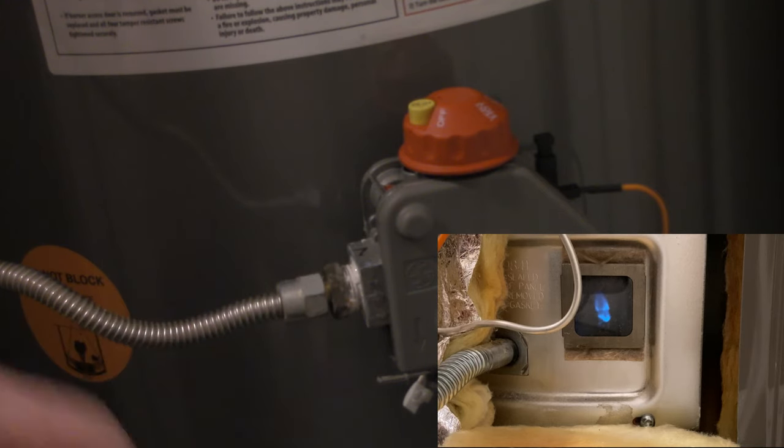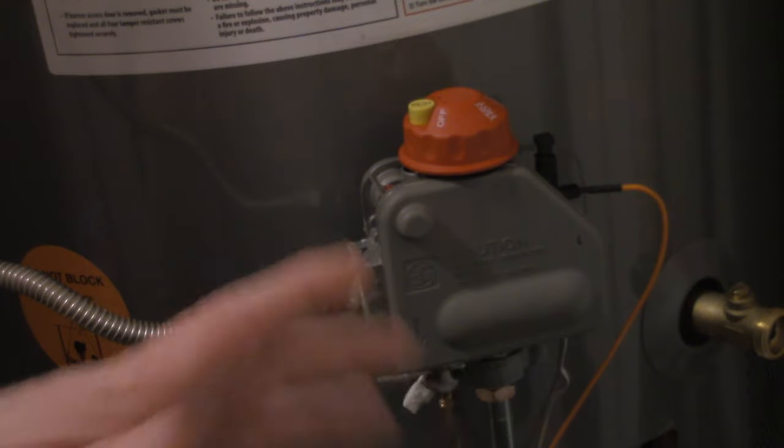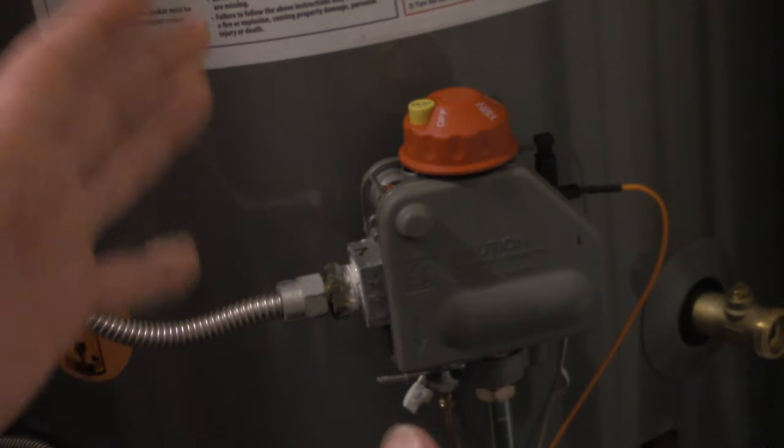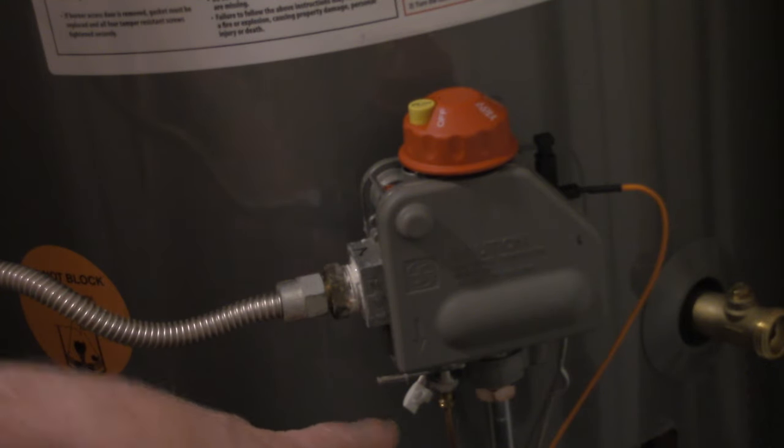Now at this point if you have done these steps and your pilot light works now, the problem is that emergency cutout switch. That's all that it could be because your thermocouple is working here just as it's designed. That emergency cutout is bad.